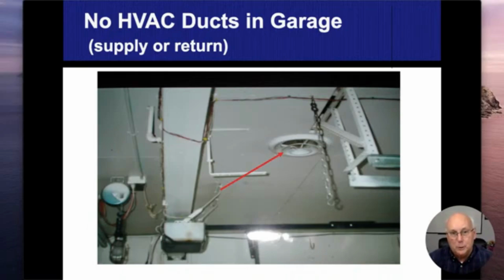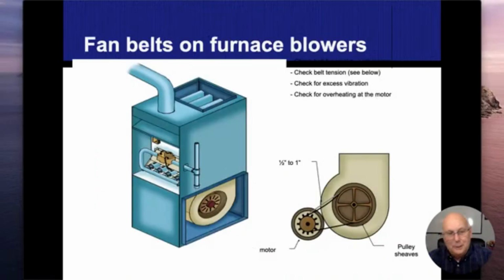Now I can run ductwork through a garage. That's not a problem. But it does have to be in a soffit. It does have to be protected by drywall. Just being out in the open isn't a good idea. There was a time frame when that wasn't considered a problem. In houses that were built after World War II, they used that garage space to get heat to different rooms. But I don't know when it changed. But in today's day, new construction, and even if I saw that, I would still say it's not a good idea, and I would do what I can to encourage somebody to get some sort of drywall or something wrapped around it, just to make it a little more airtight.